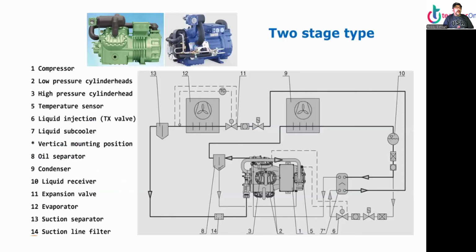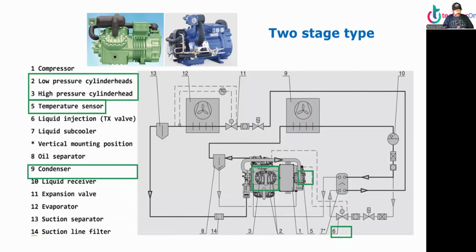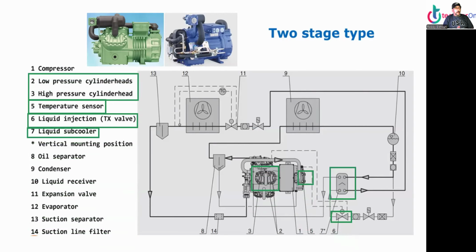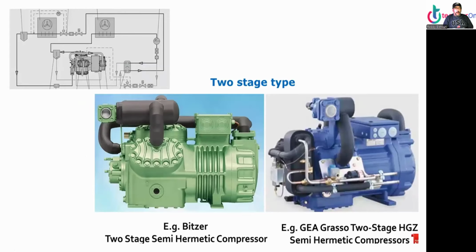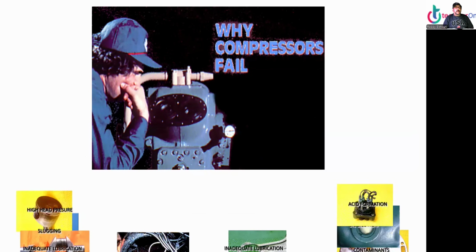Okay. And we have also two-stage compressors. I never worked on one, only in books. There's more going on. We have a low pressure cylinder, high pressure cylinder. We have temperature sensors, liquid injection TXV, liquid subcooler, and suction separator. I think they mean the suction accumulator, maybe, probably. But I just put it in there so if you see a compressor with 4 valves, 4 pipes coming in and out of it, then you know it's a 2-stage. That's for ultra cold freon. Alrighty, 2-stage. Now, why compressors fail, let's go to troubleshooting.